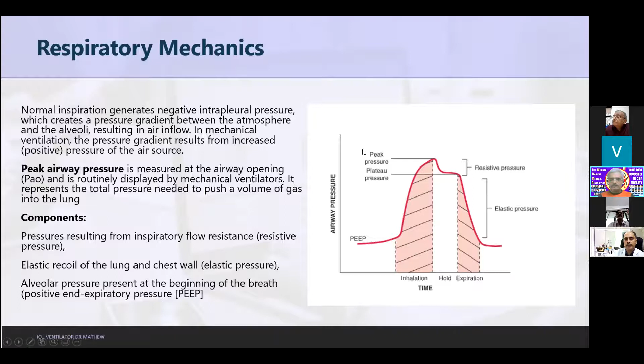The moment you start breathing, there is already a positive pressure in the lungs, that is PEEP. This is also adjustable by ventilators. Now, the means and modes of mechanical ventilation: there could be volume cycled ventilation or pressure cycled ventilation. Volume cycle means that we set a volume of air that has to be pushed in with each breath, that is the tidal volume, and usually it is set as per the weight of the patient. So volume cycle delivers a constant volume with each breath.